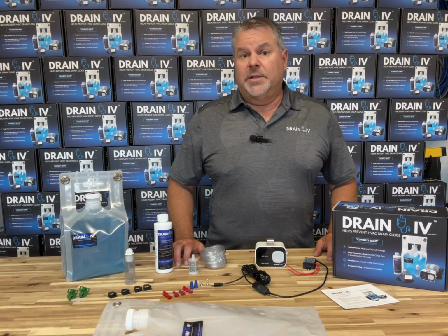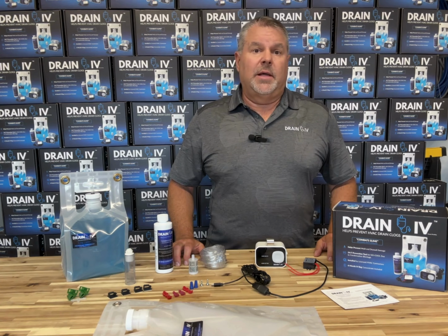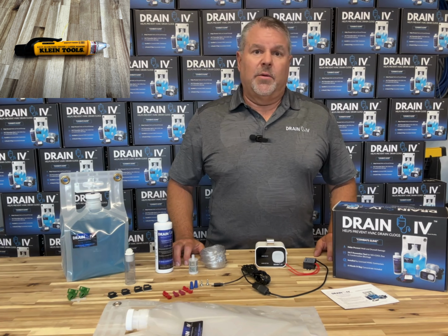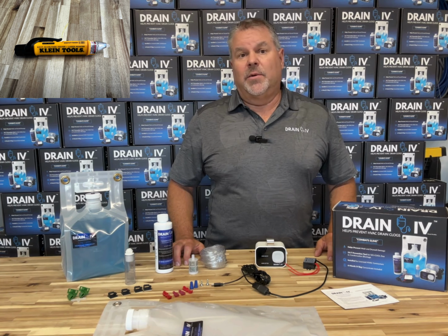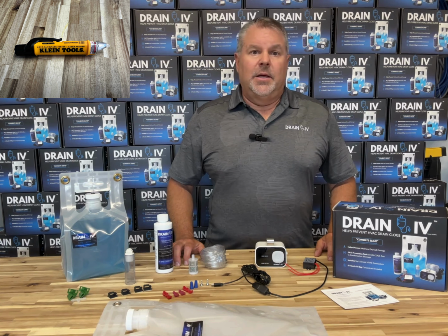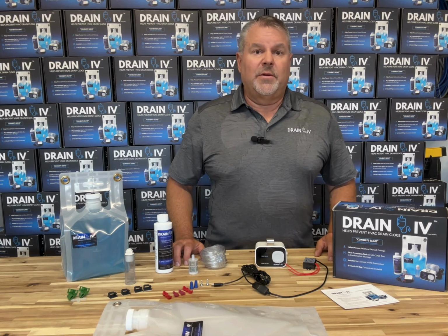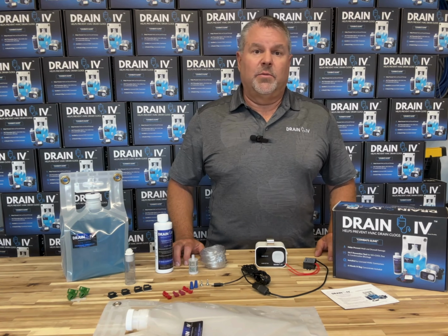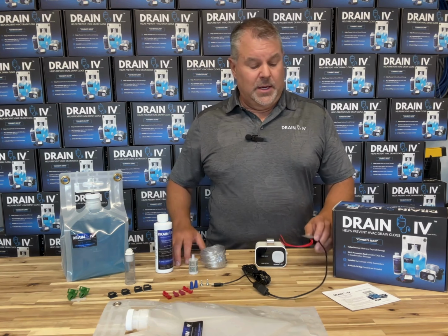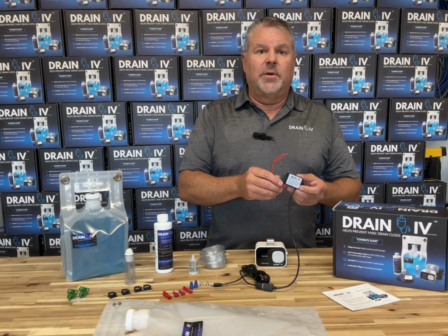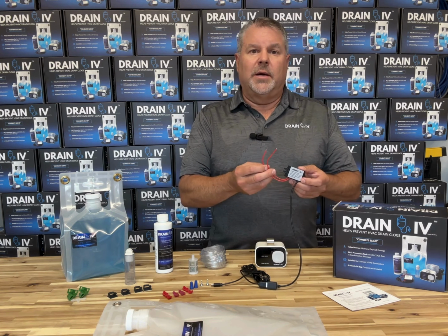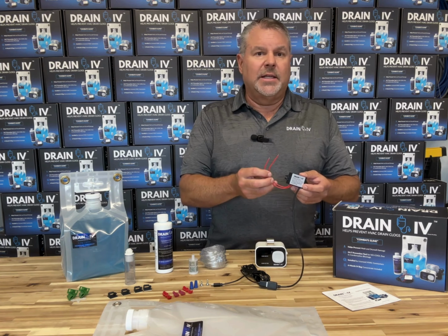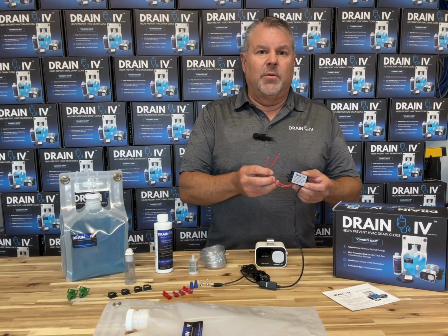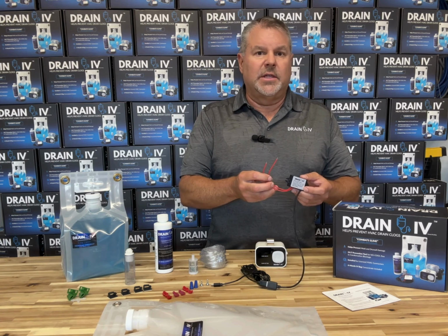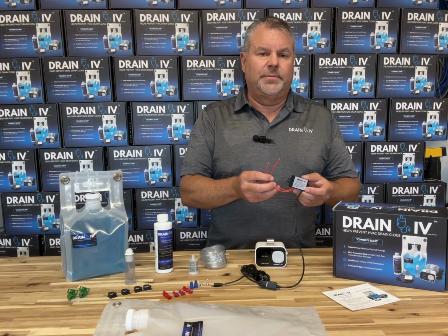First, as noted in housekeeping, you will want to turn off the power to the air handler. Being a stickler, I always like to double check with a non-contact voltage tester. Using your screw gun, remove the cover on the air handler's control box and locate the 24-volt AC transformer. On the 24-volt to 5-volt converter, there are 2 red wires. These wires are to be connected to the low side of the transformer with either red wire to either side of the transformer with no polarity concerns.